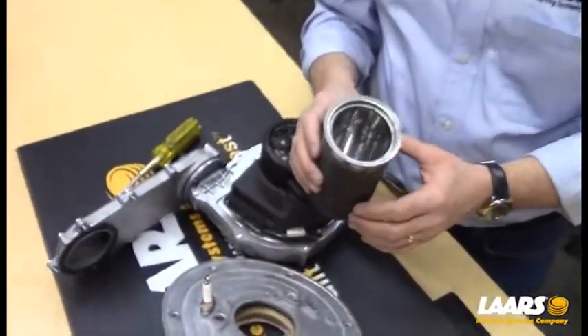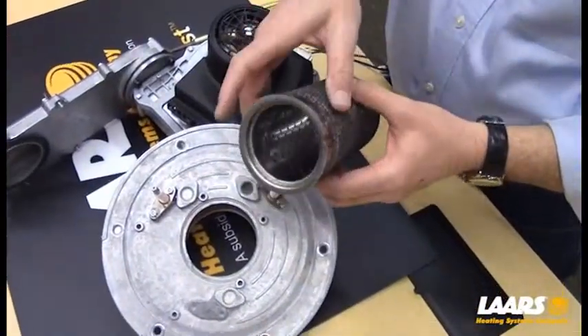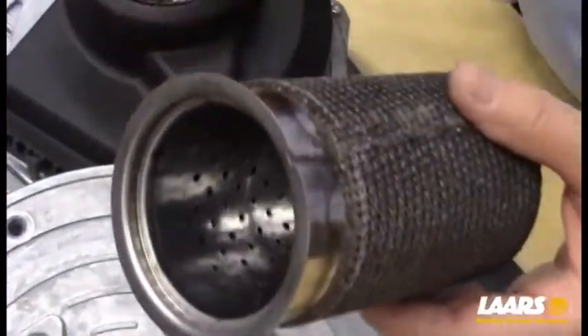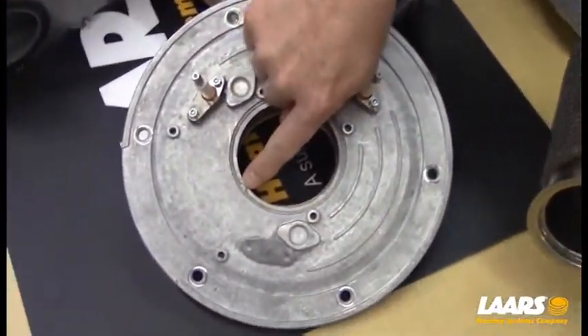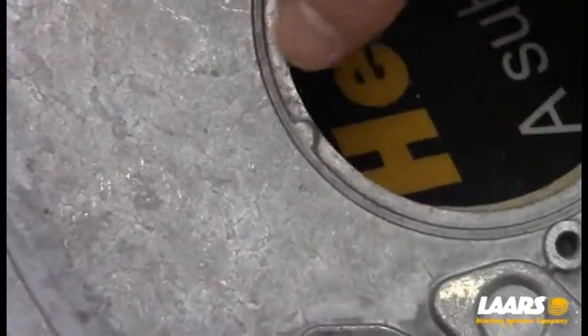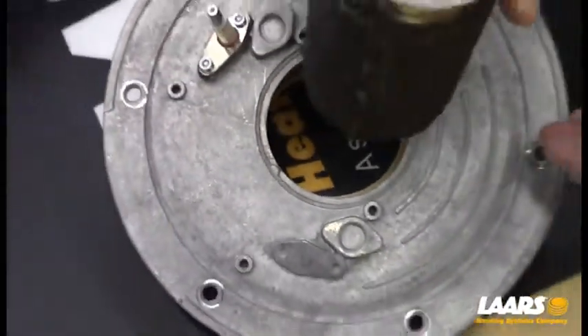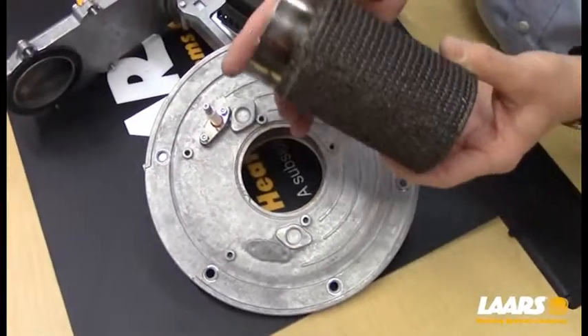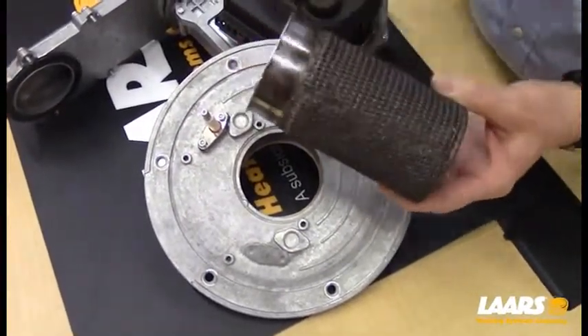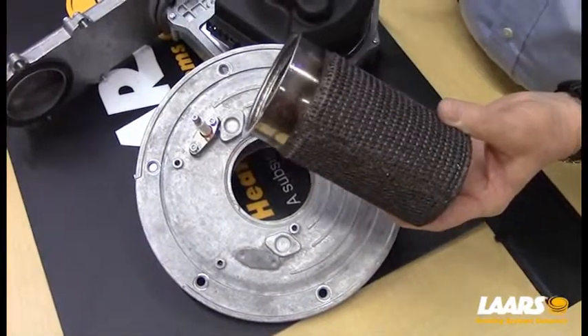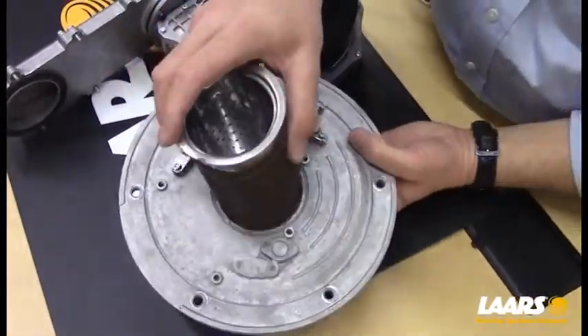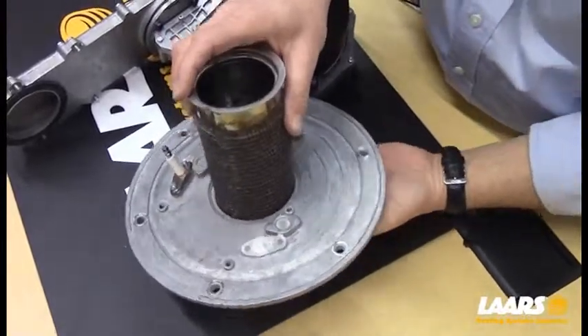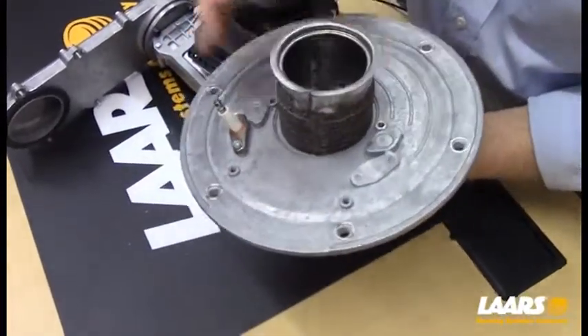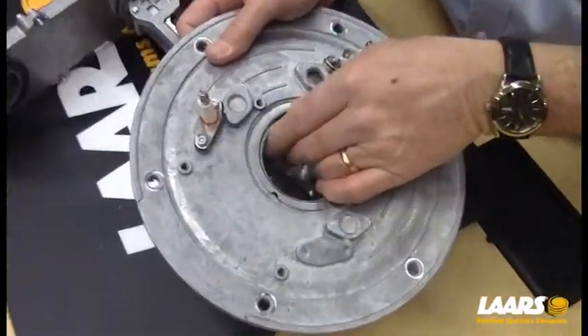So one of the other things I want to point out when you're putting this back together, providing this is clean or if you needed to clean it, there's a little half-moon dimple on the burner. That lines up with the half-moon dimple on the casting of the burner plate. The reason we want to line that up is that's where the seam is for the mesh on the burner. You don't want that near your ignition point. So very simply, you're going to gently push that back into position. Again, we do not want to destroy the refractory block on the back side. Then line up your half-moon dimple.